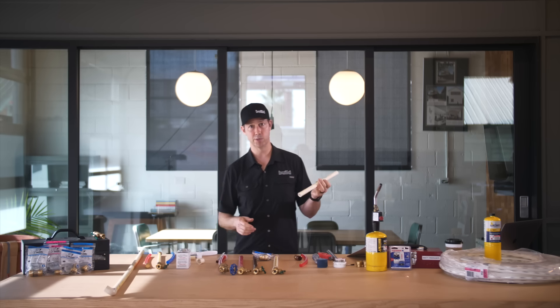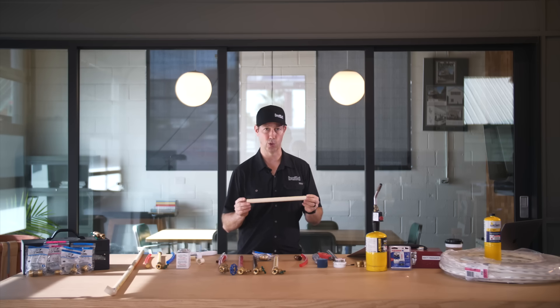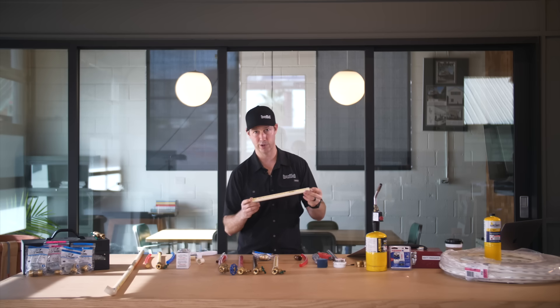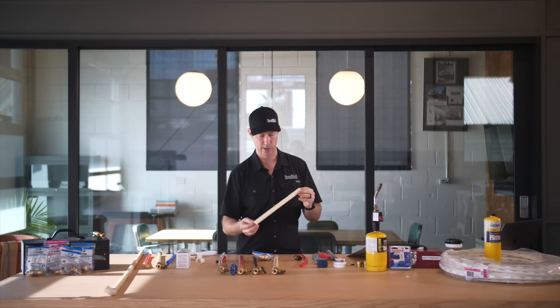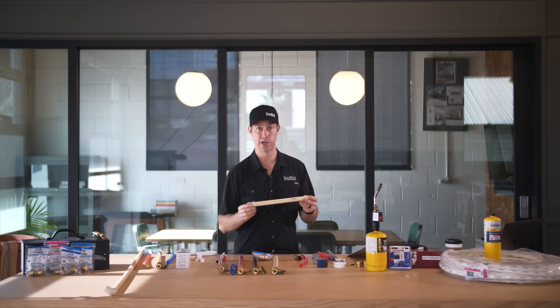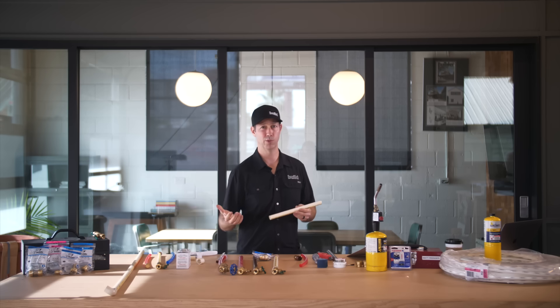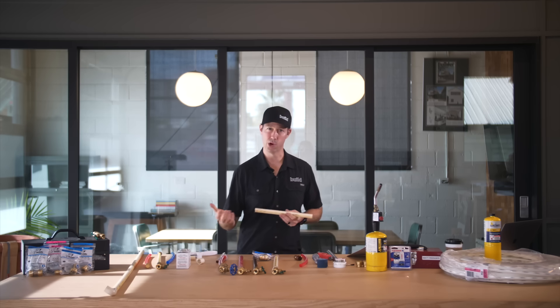CPVC has actually been around a long time — since the early 1960s. I believe FlowGuard Gold is the only manufacturer at this point. This is different from PVC; it's chlorinated polyvinyl chloride piping, a different chemistry. It has a little flexibility and is very resistant to chemistry in the water, so if you have issues with well water or other things that might eat pipes, this is a great choice. When it comes to cost, this is probably the least expensive pipe in our inventory — very cost-effective. You have a little more labor than PEX but less than copper, so overall it will certainly cost less than copper and maybe slightly more than a PEX install.